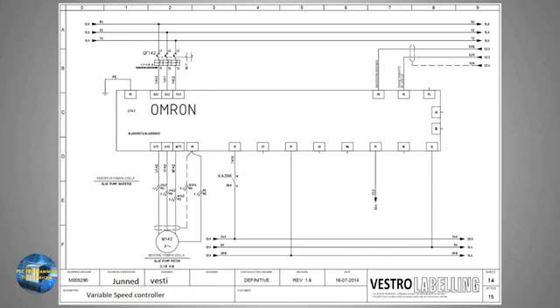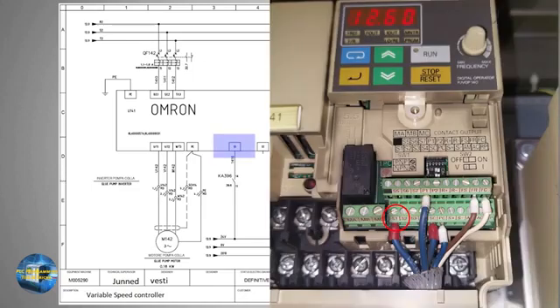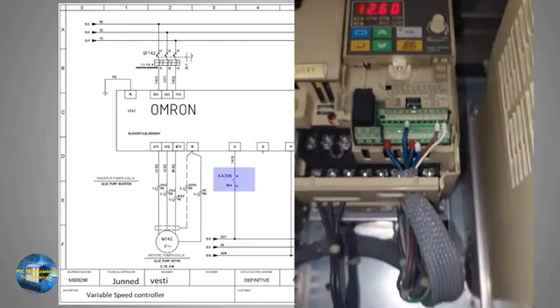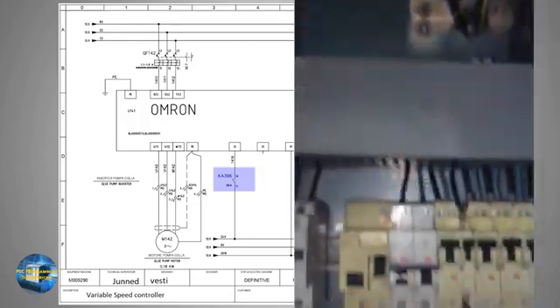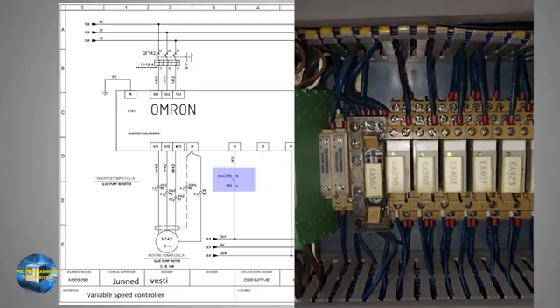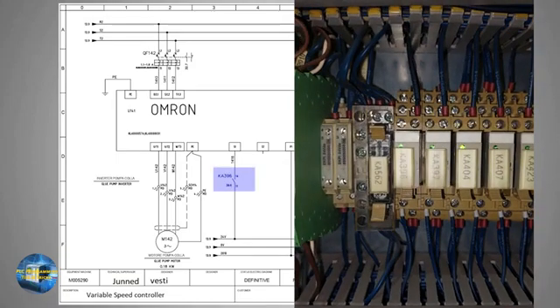VFDs normally require a run command signal from the PLC to turn on the motor. The S1 is a digital input terminal of the VFD. This terminal receives a run command signal from the PLC. If you look closely, this signal is coming from the normally open contact of the relay KA396.